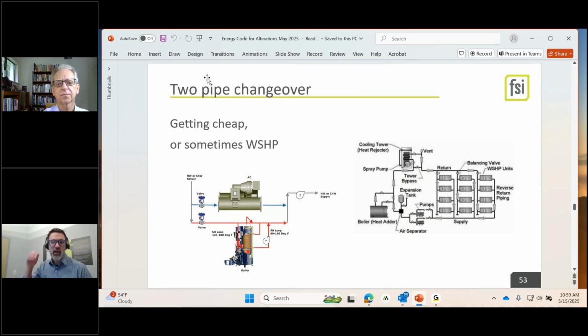It's all interesting. Two pipe changeover, the cheapest of the cheap systems. You run cooling in the summer, and then you turn on the boilers and turn off the chiller and run heating in the winter. It's all through the same pipe, and so that's not great, and certainly has occupant comfort issues. But it presents this super exciting thing where you can say, oh, great, I'm going to start running it as a water source heat pump loop because you have a similar delta T. The pipe sizes don't change if the piping's in good condition. Put an air to water chiller on one side doing those low temp or medium temp loop temps.